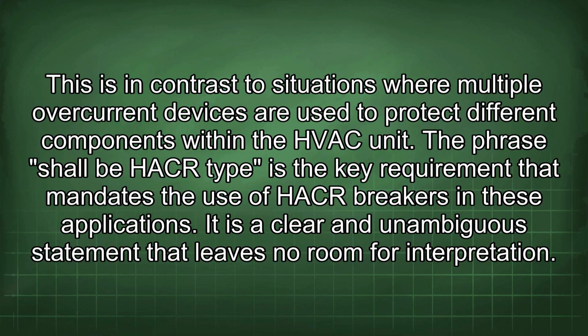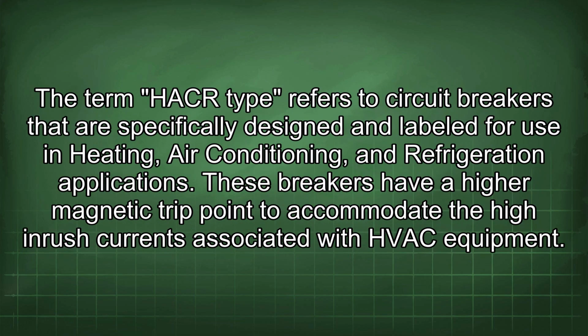The phrase shall be HACR type is the key requirement that mandates the use of HACR breakers in these applications. It is a clear and unambiguous statement that leaves no room for interpretation. The term HACR type refers to circuit breakers that are specifically designed and labeled for use in heating, air conditioning, and refrigeration applications.